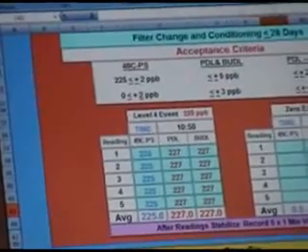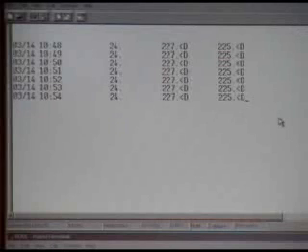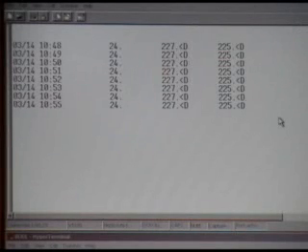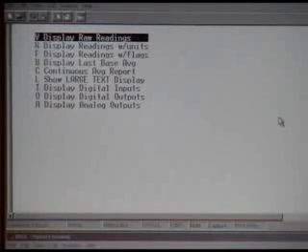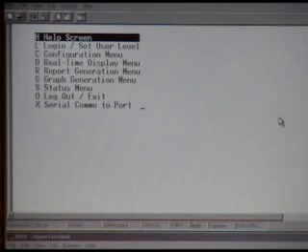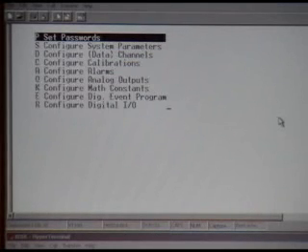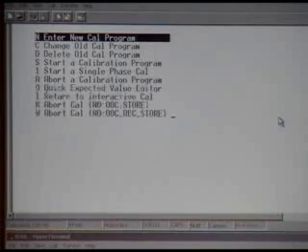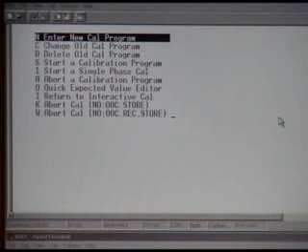Now we're ready to stop this event and start our 0 and fill that in. And we'll show you how to stop this event. You want to press escape, escape again, and escape a 3rd time. C for configure, C again for calibration configure. We want to abort our cal event. W, give there a click. After we hit 03, enter. Hear the click, it means the event is stopped.